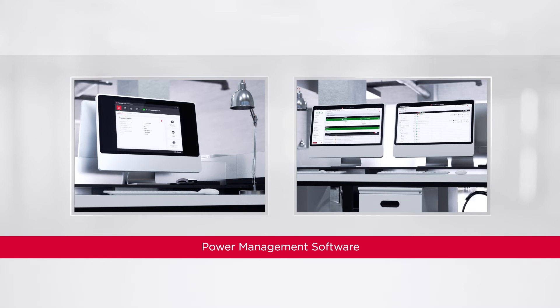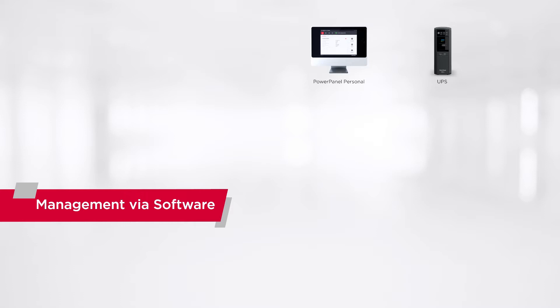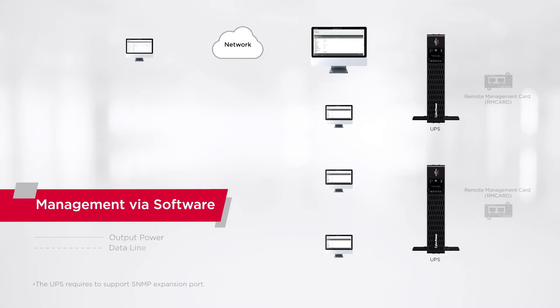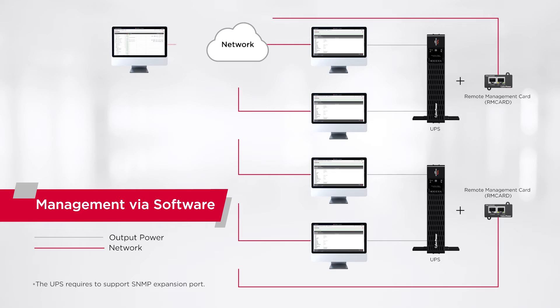You can also manage the UPS systems through CyberPower management software, which allows different alternatives in regard to installation and settings. For single UPS management, you can install the PowerPanel Personal software and connect the UPS to your computer through a USB or serial cable. For multiple UPS systems installed with an RM card, using PowerPanel Business remote and management modules allows you to control and monitor all UPS systems simultaneously.